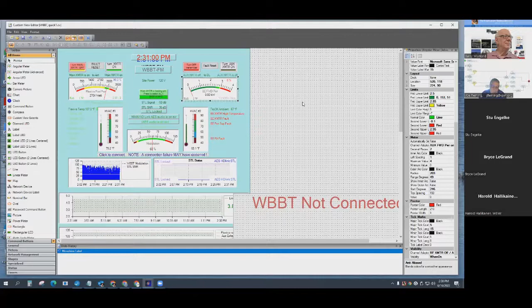That's on the very far bottom section here, on the lower right. What I do is look at the status of when that transmitter says it's on — that's the only time I show that meter. So if I go out there and do testing for 20-30 minutes, turn it on, make sure everything's good, take a bunch of readings, it'll show on this screen for that 20-minute duration.